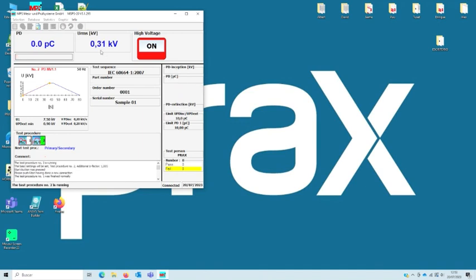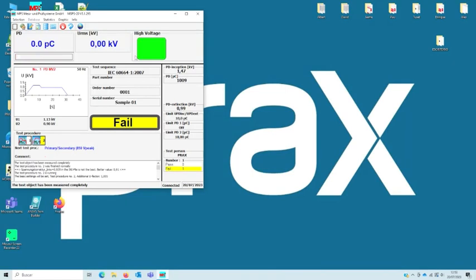So now here you can see how we are increasing the voltage, and this voltage is increased until reaching more than 10 picocoulombs. Here you can see the partial discharge that we are measuring now. Then we wait around 10 seconds to stabilize the partial discharge, and then we continue reducing the voltage. Here you can see that the extinction voltage is 1 kilovolt, so it means that the maximum working voltage between primary and secondary side would be 1 kilovolt. Considering that this is RMS voltage, the real maximum peak voltage between primary and secondary side would be 1.4 kilovolts.